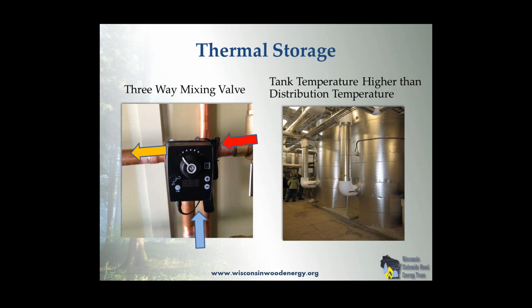So what you need in every case of thermal storage is a way to store the water from the boiler at a higher temperature than you're going to deliver it to the system. That requires some mixing valve on the return and the delivery side of the system, or some way to blend or mix in water from thermal storage into an existing system.